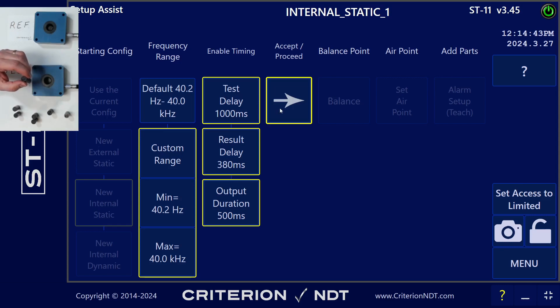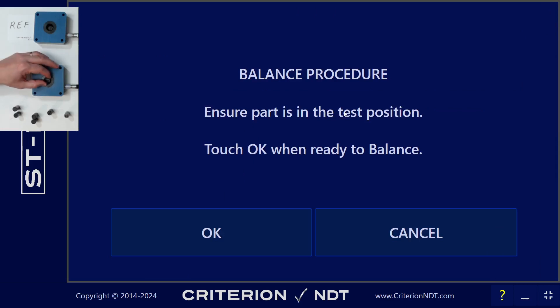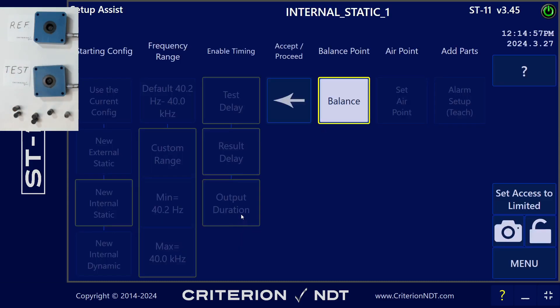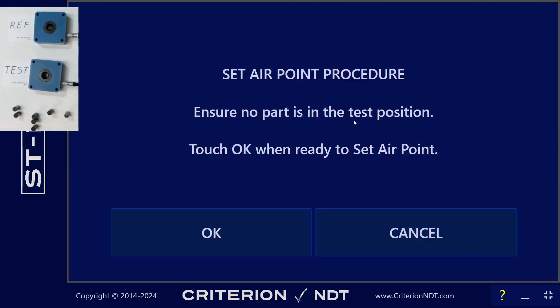So I'm going to proceed to the next step, because all of these settings look just fine, and balance. We'll put the part into the test coil. I'm going to position it up against the edge of the coil, and then hit OK. After the balance routine runs, I'm going to remove the part from the coil and set the air point. This reminds you of what to do, and hit OK.